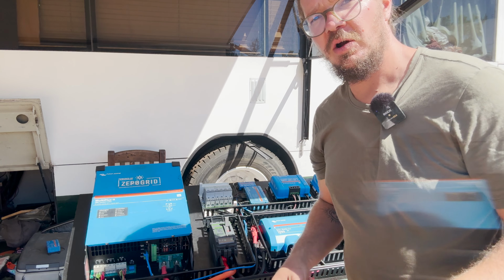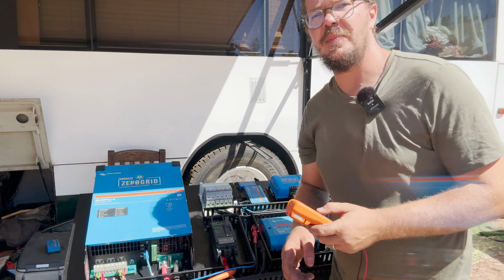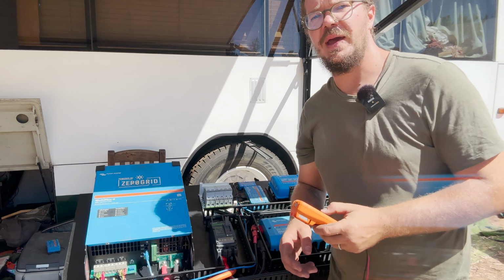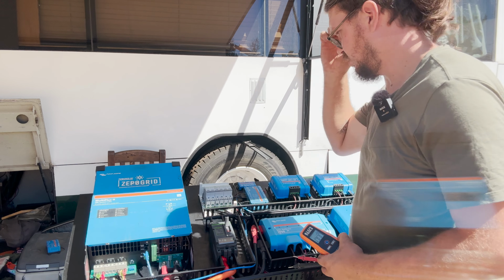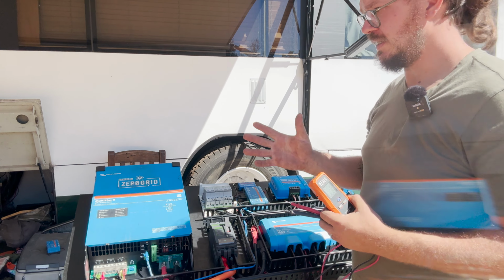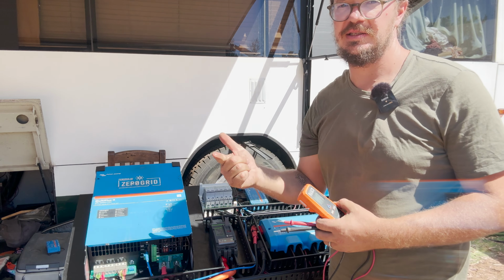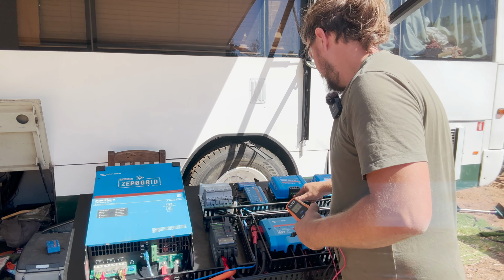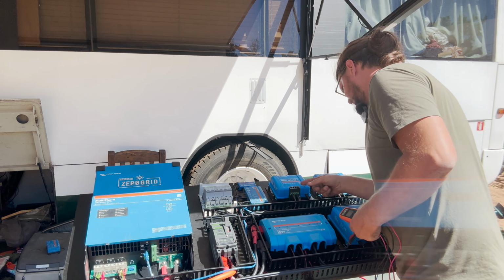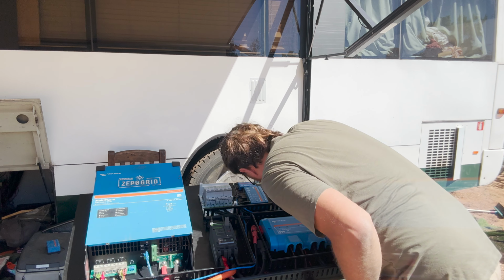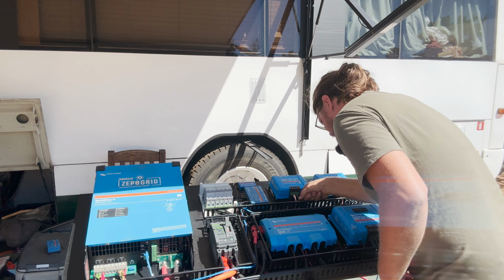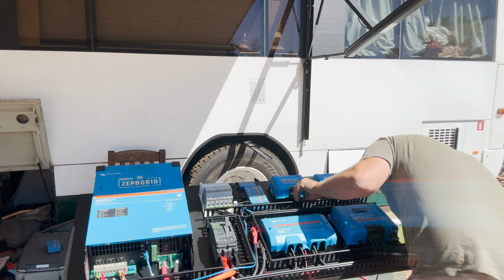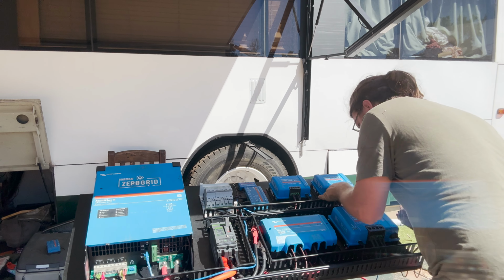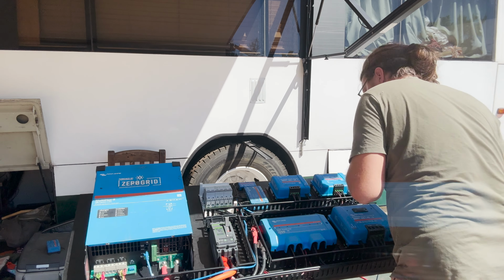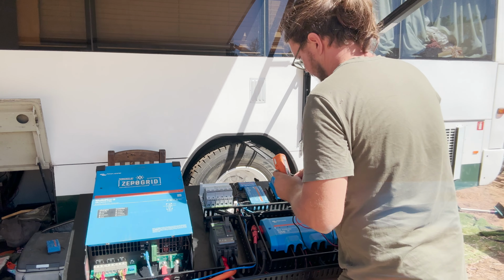Where I was at is explaining about - you remember better than I did, I suppose - checking polarity is such a huge thing, an easy thing to get wrong. So there's the visual check, and then there's testing with a meter. What I'm doing is checking to make sure the cables with the line on them are in the positive hole, because the positive cables - that's that one there - positive, negative, negative, positive.